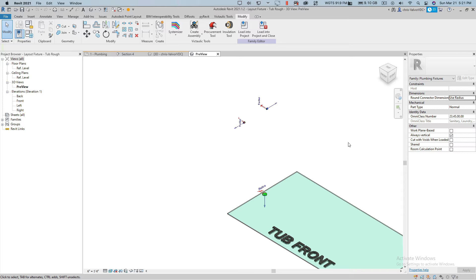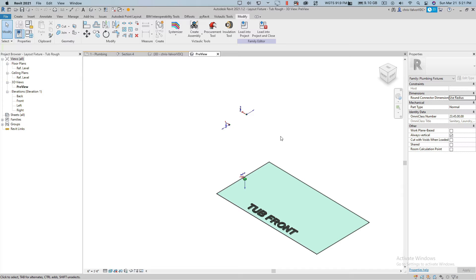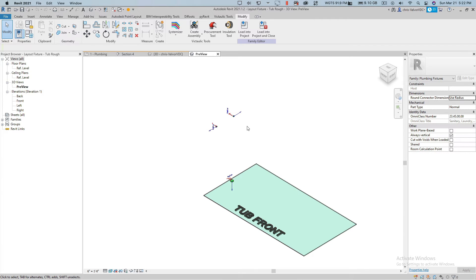Quick caveat: fabrication fittings don't care what the connector is. They're just kind of dumb catalog items that have been put into Revit that don't actually give you any real value or information. That's why I quit using fabrication ITM parts and I'm back into Revit families — because I want to get the information, I want connected systems, I want to be able to read things across and have these checks and balances. My team was having a lot of issues when they would connect things and sometimes they wouldn't run the right systems, especially when you get into high pressure water systems.